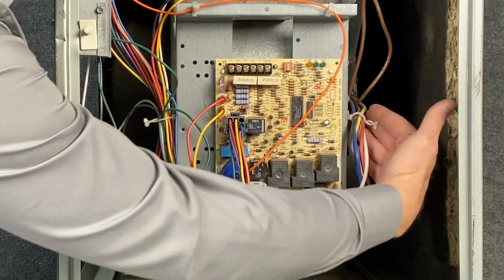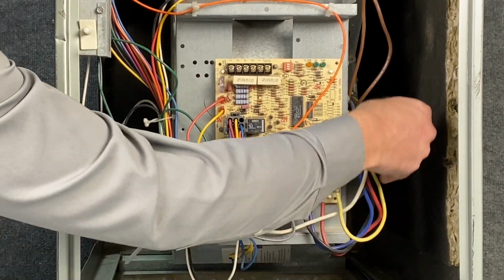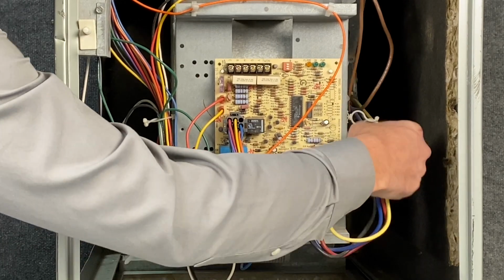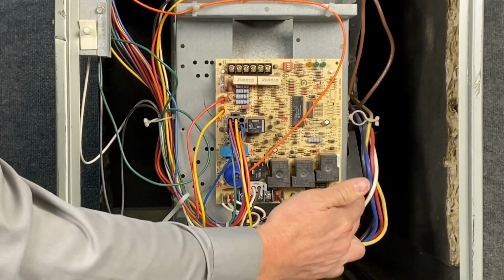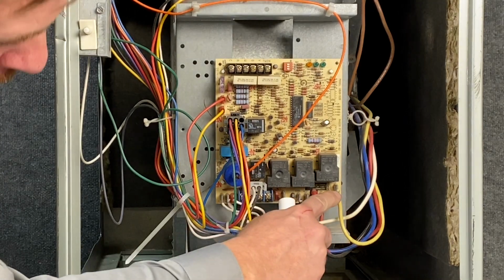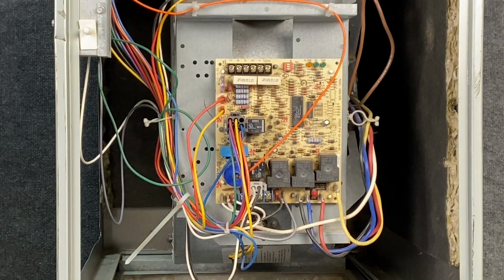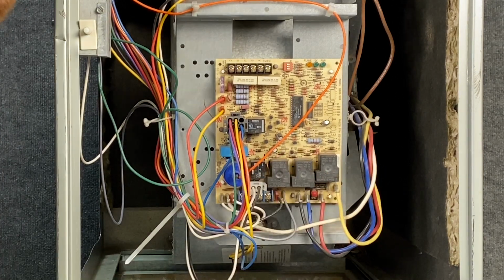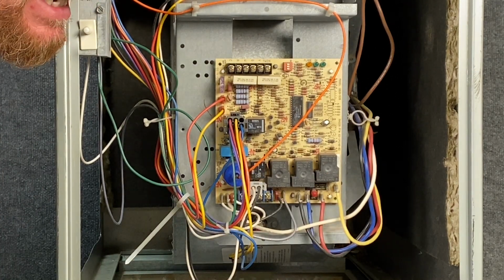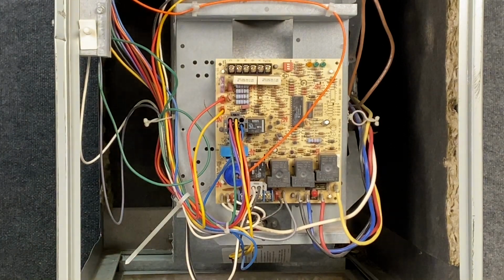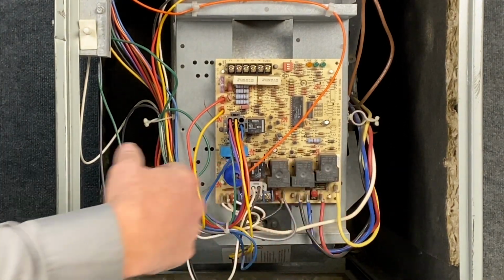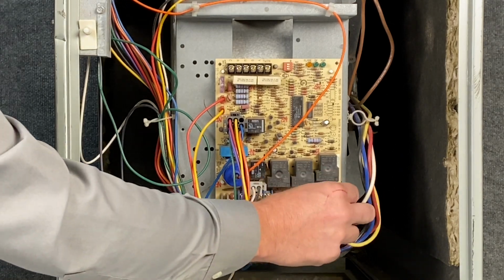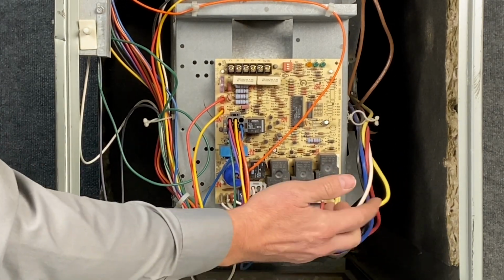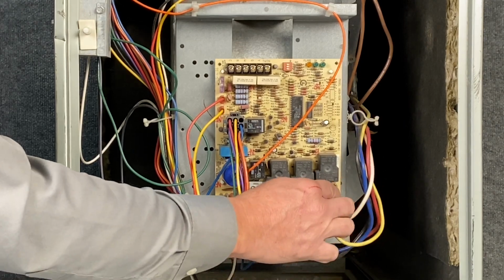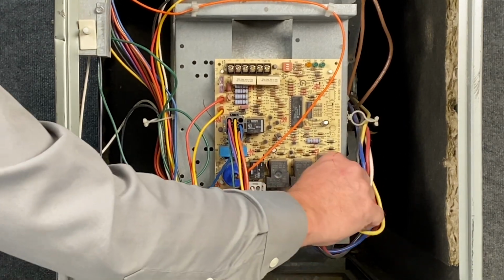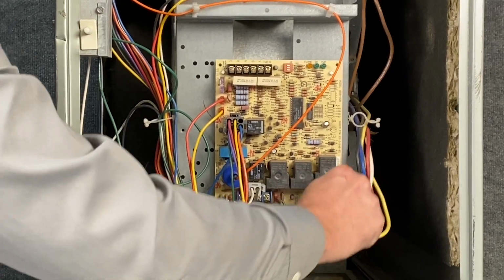So here's our blower motor on the back, and we have these wires in this nice little wire connector. So if we loosen that up, these are the wires just for the blower motor. So we're going to start here, and this yellow wire is on a terminal called M2. You don't really need to know what M2 goes for. We just need to be able to mark it. Yellow wire is on M2. Now, so you know what M2 goes for, M2 doesn't go to anything. It's a hold or a park terminal. It's just to use that extra wire. So in other words, this yellow wire is a speed that we're not currently using, and it's just to hold that wire out of the way. Either way, we marked yellow was M2, so now we can take this wire terminal loose.